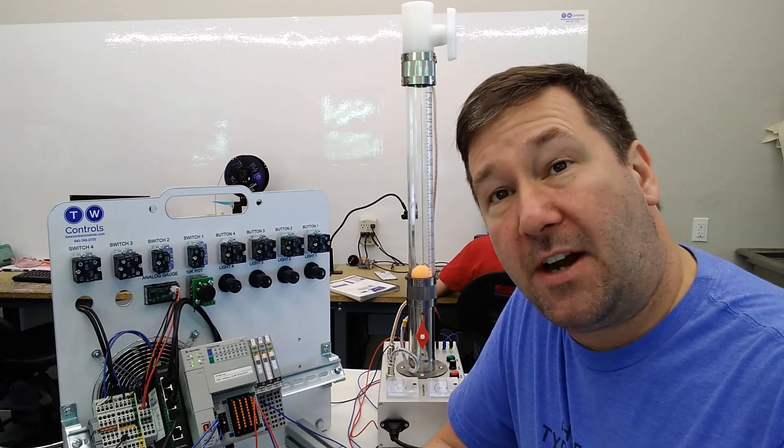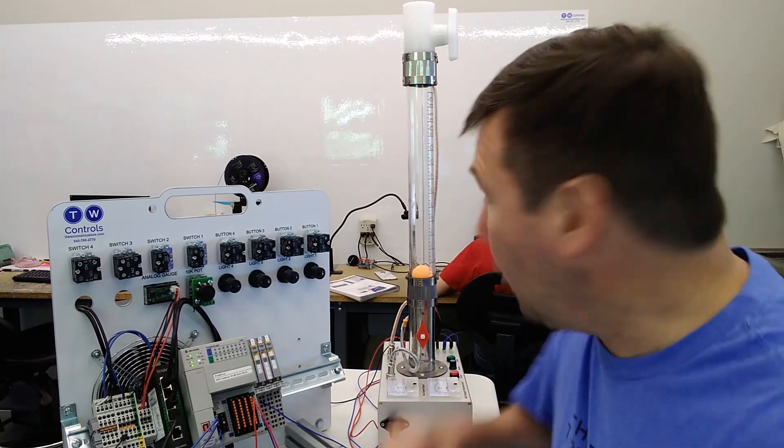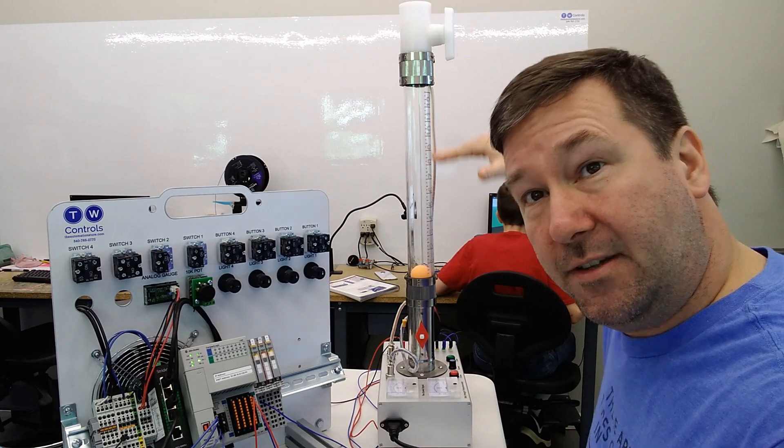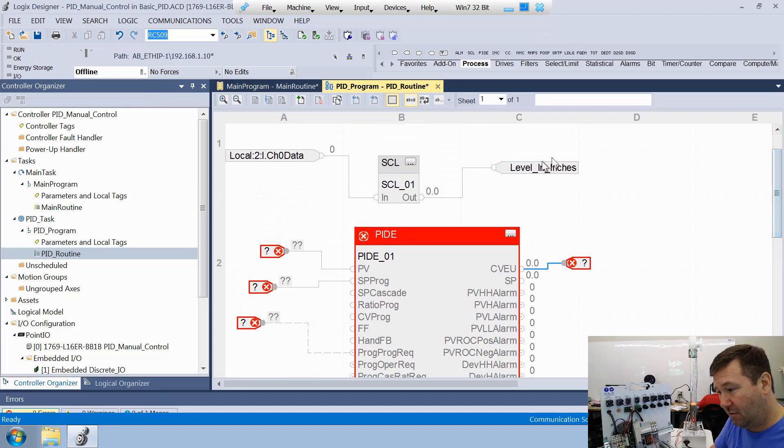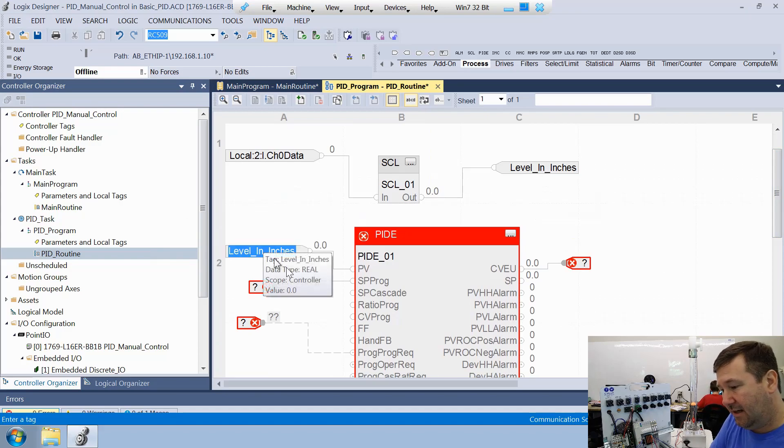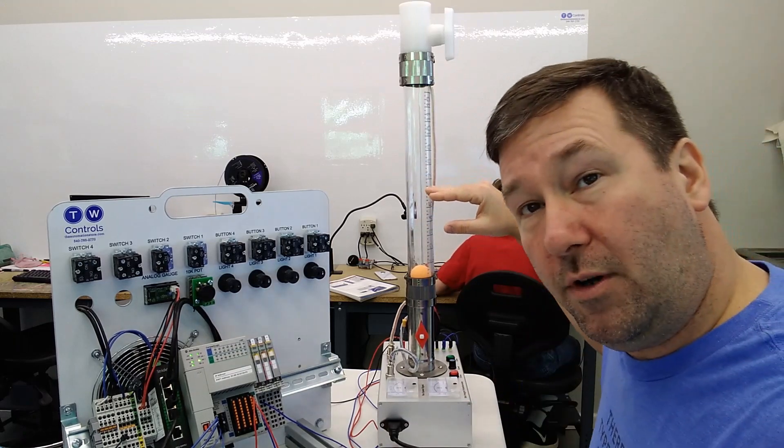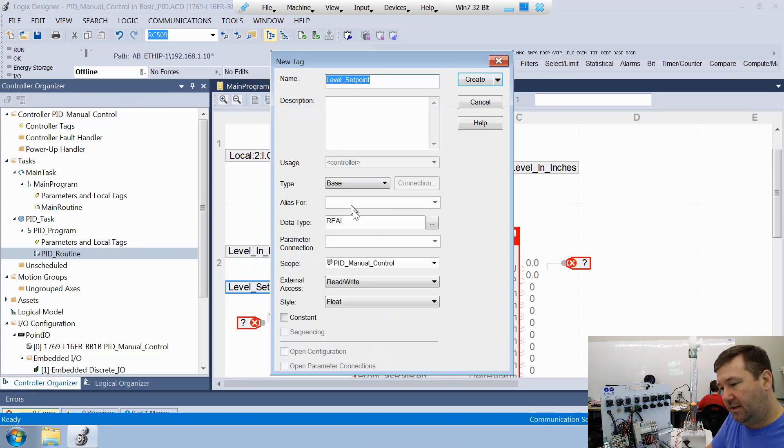Okay, so our process variable is the thing that we're trying to make the output force to be in a certain spot or our input. So I want my level to be, let's say six inches. So our process variable is this level and we've already scaled it. It's in this SCL instruction right above level in inches. So let's put that here. And then our SPProg, that is the set point that we're wanting. And we're going to create a tag for it. So let's call it level set point.